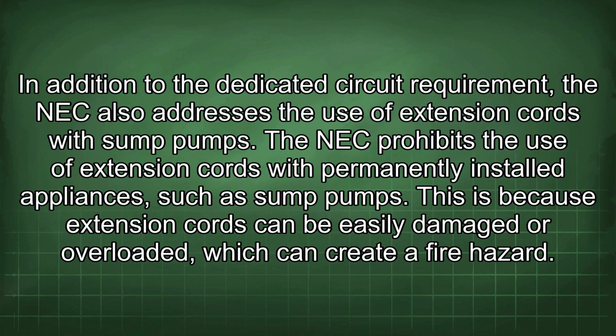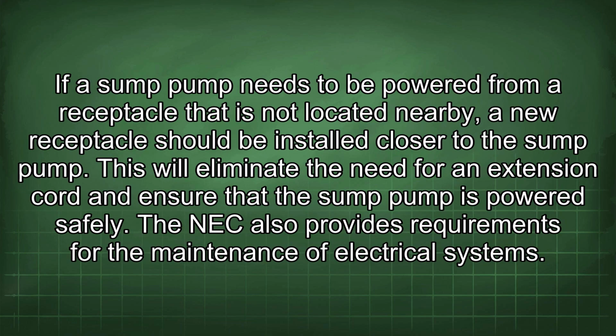In addition to the dedicated circuit requirement, the NEC also addresses the use of extension cords with sump pumps. The NEC prohibits the use of extension cords with permanently installed appliances, such as sump pumps. This is because extension cords can be easily damaged or overloaded, which can create a fire hazard. If a sump pump needs to be powered from a receptacle that is not located nearby, a new receptacle should be installed closer to the sump pump. This will eliminate the need for an extension cord and ensure that the sump pump is powered safely.